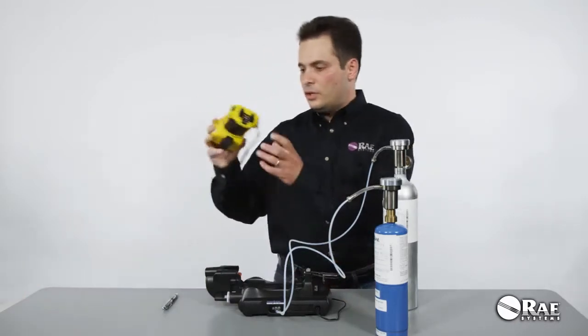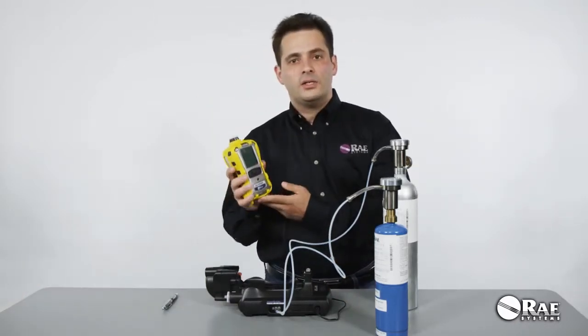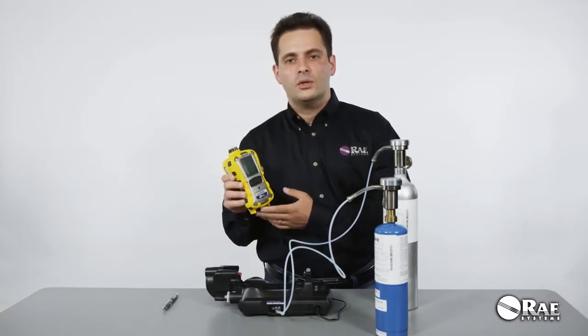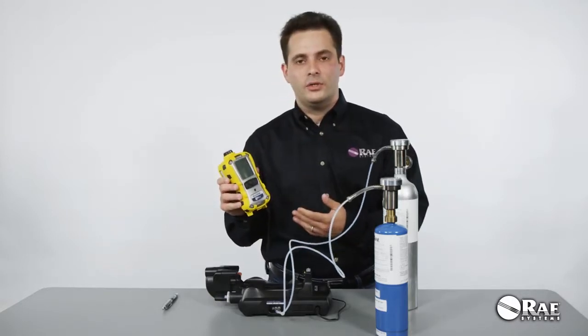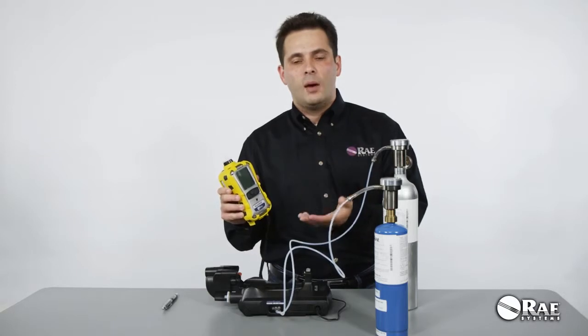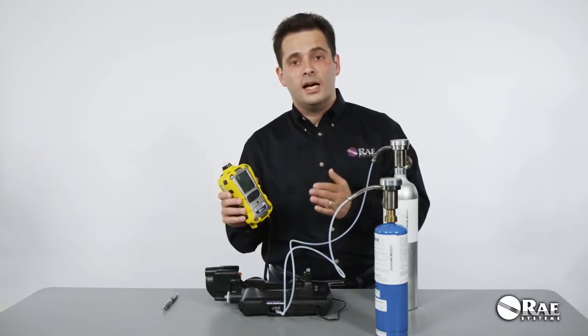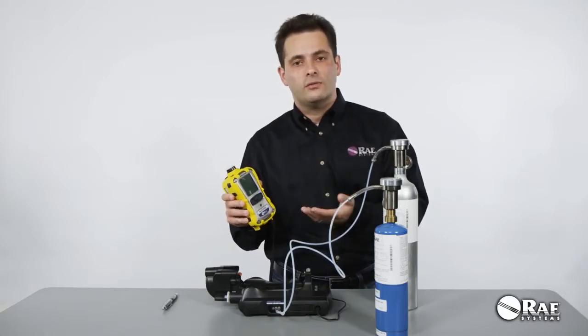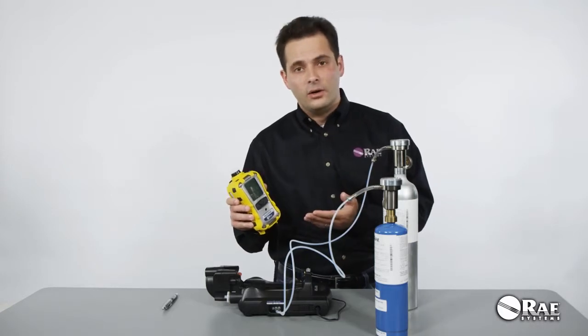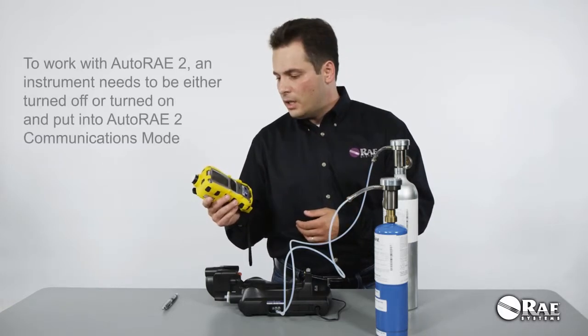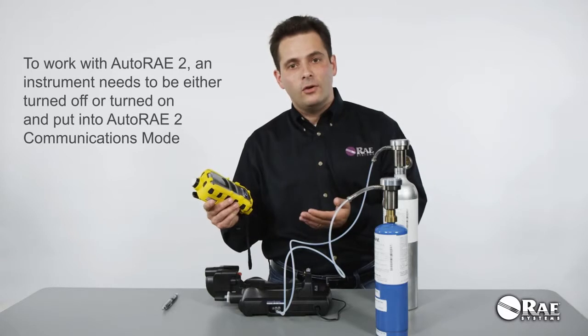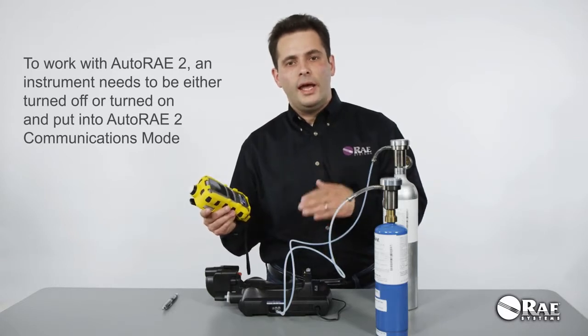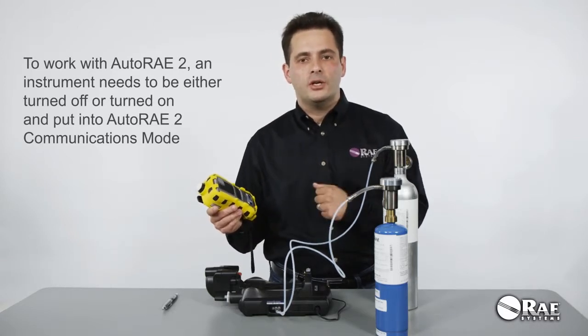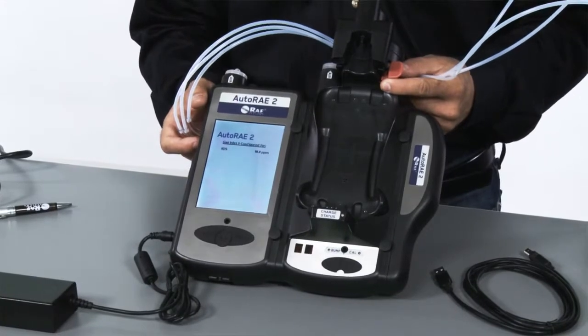All you need to do is make sure that your MultiRAE has compatible firmware in it so that it can be recognized by the AutoRAE 2, and that firmware is application firmware version 1.10 or higher and sensor firmware 1.03 or higher. And then your MultiRAE needs to be either turned off or it needs to be turned on and put into the AutoRAE 2 communications mode. The system is now ready for use.